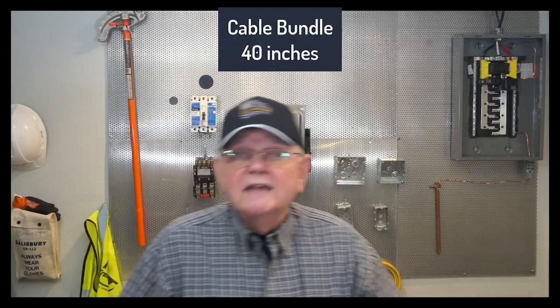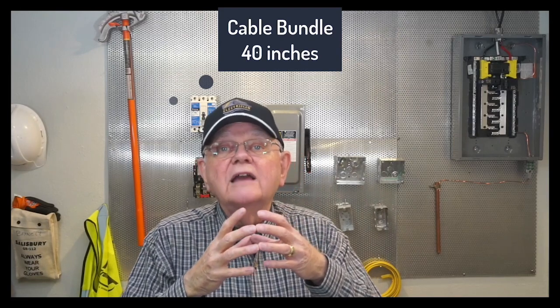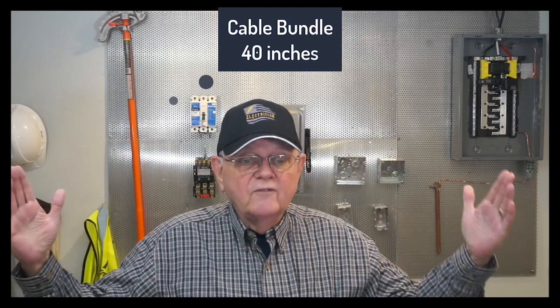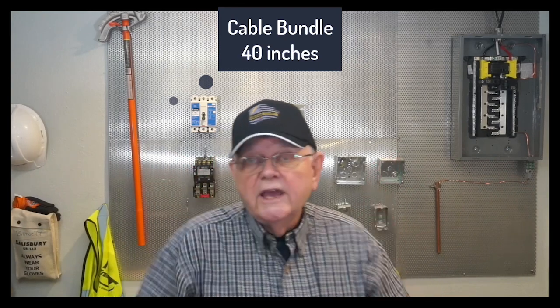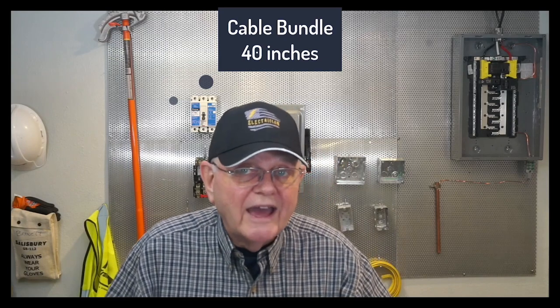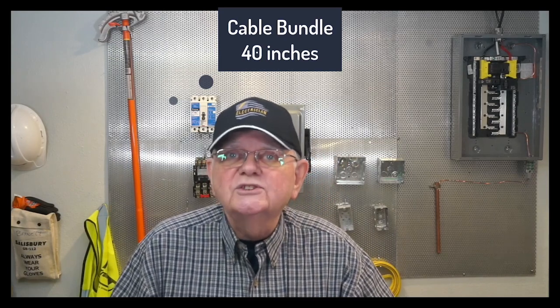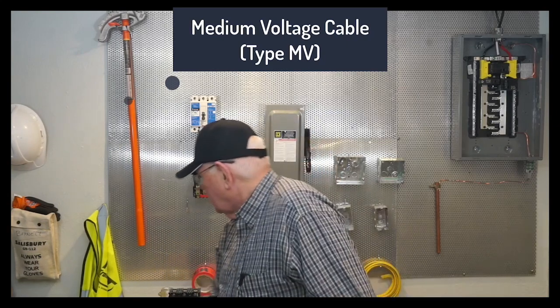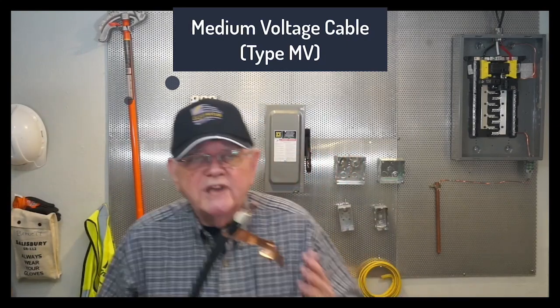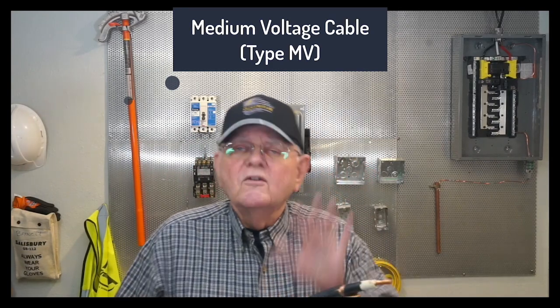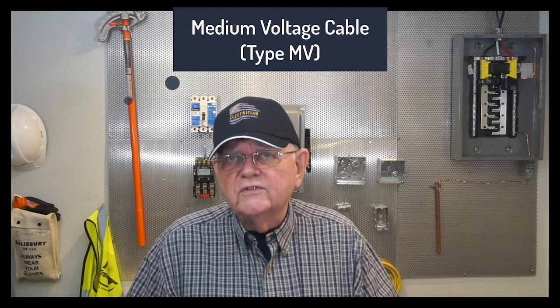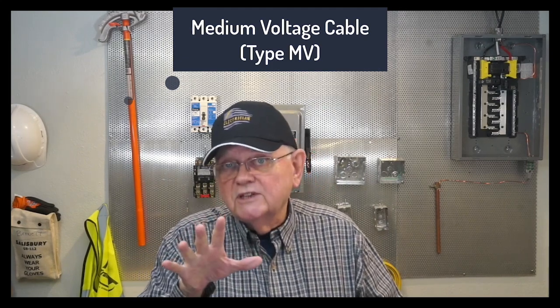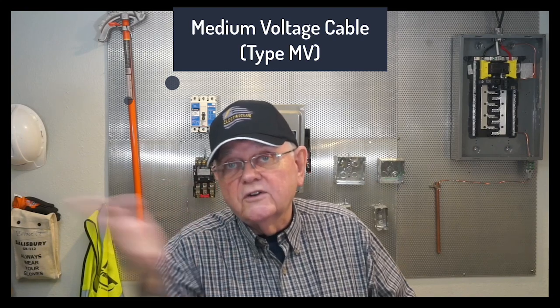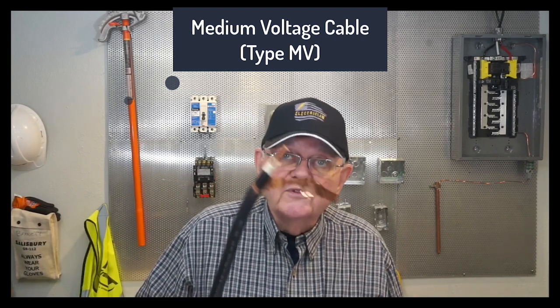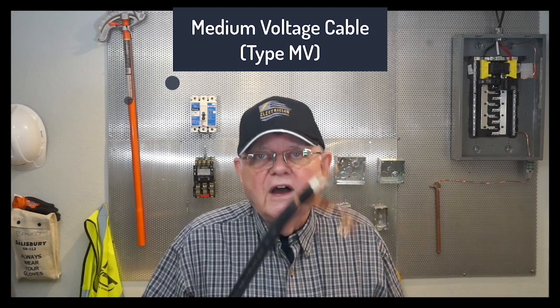31 different types of cable, a cable bundle. So I group my cables together for how long? At least 40 inches. If I don't have 40 inches, I don't have a cable bundle. An informational note tells you to be careful if you're going to do that, because you can cause overheating problems, can't you? Medium voltage cable. Now there's a definition for medium voltage cable, and it says cable that's rated from 2001 to 35,000 volts. That's kind of interesting if you think about your definitions. I just told you high voltage is anything greater than 1,000 volts, and now we've got medium voltage cable at 2001 to 35,000 volts.